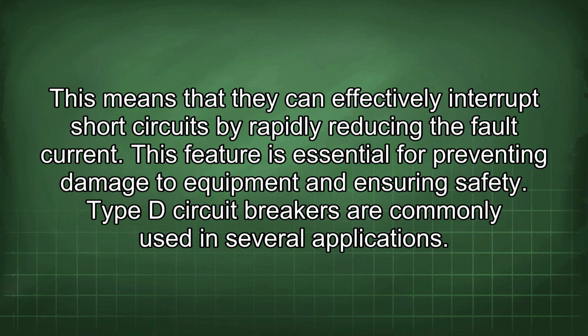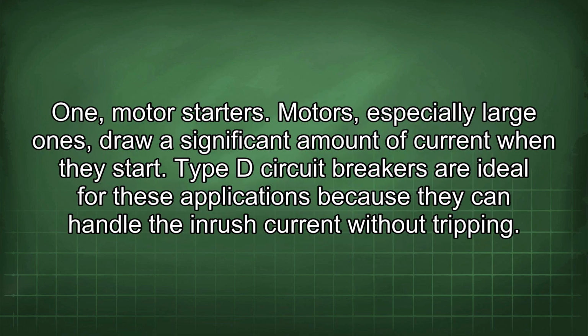Type D circuit breakers are commonly used in several applications. 1. Motor starters. Motors, especially large ones, draw a significant amount of current when they start. Type D circuit breakers are ideal for these applications because they can handle the inrush current without tripping.